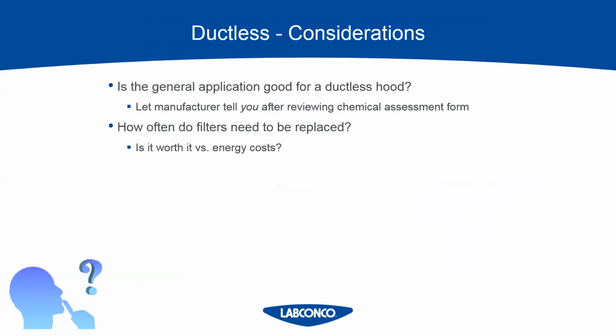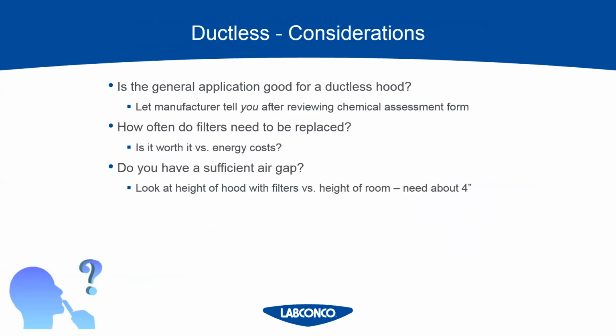But if it's a short filter life, is it even worth the cost of changing those filters out versus the installation and energy cost? So you have to weigh that on a case-by-case basis. Does your room have a sufficient air gap? This is something that gets overlooked with ductless hoods. On a ductless hood, there needs to be a 4-inch air gap above the filters, because that air is going through the filters and being recirculated into the room. Some people want to shove the hood up against their ceiling and they wonder why the hood isn't working. That air needs some place to go.